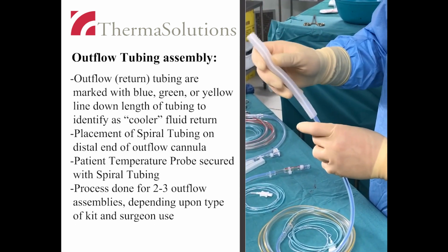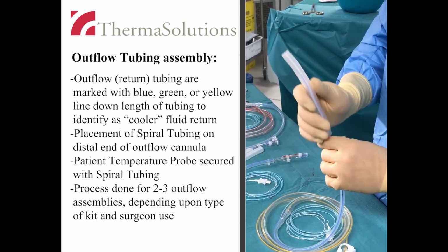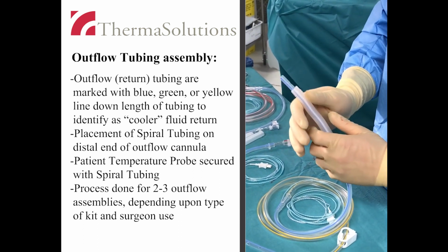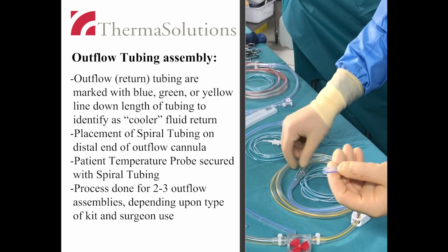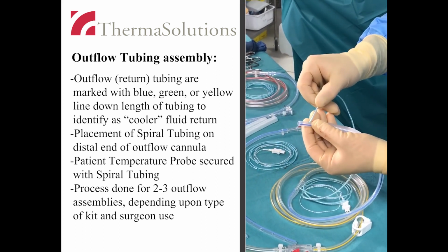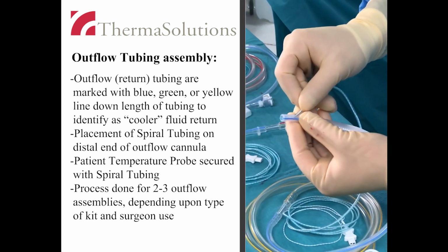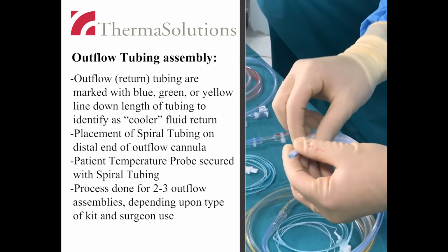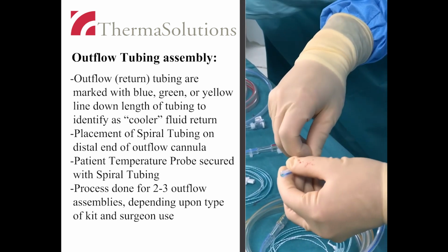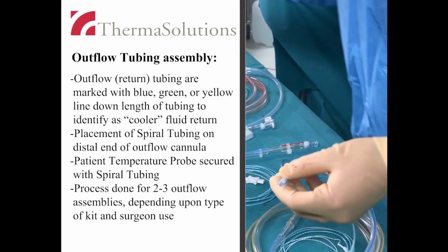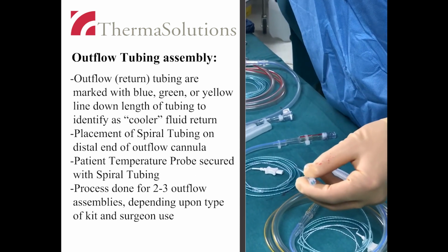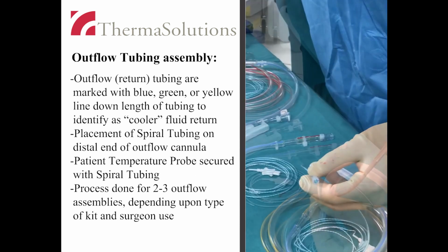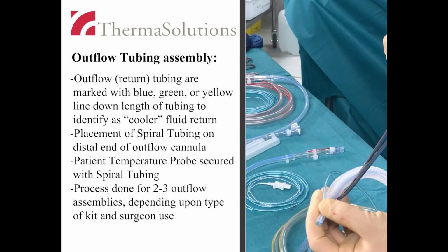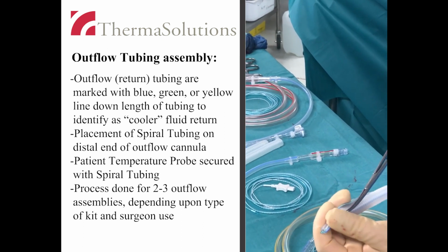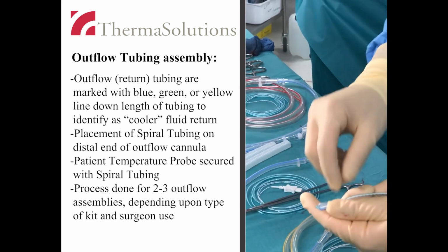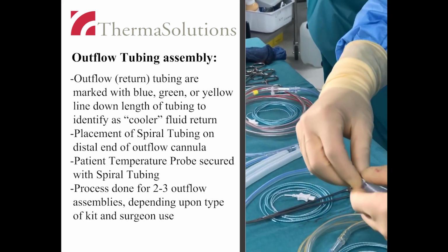Assembly of the outflow tubing involves tubing that contains a blue, green, or yellow stripe on the tubing. These colored stripes identify the tubing as outflow. The spiral tubing is first placed on the distal end of the outflow cannula. A temperature probe is inserted into the side of the cannula. The distal and proximal ends of the spiral tubing are used to secure the temperature probe to the outflow cannulas. This process is done for all outflow assemblies.